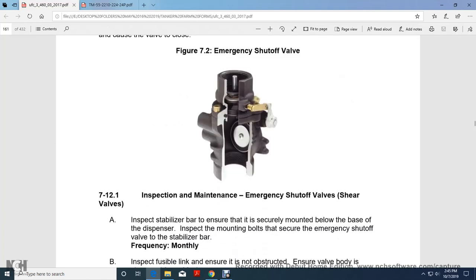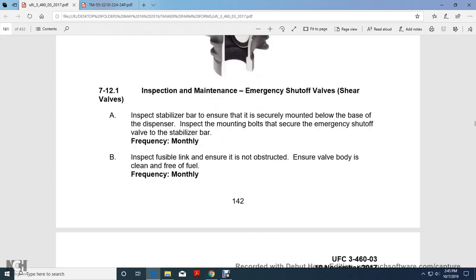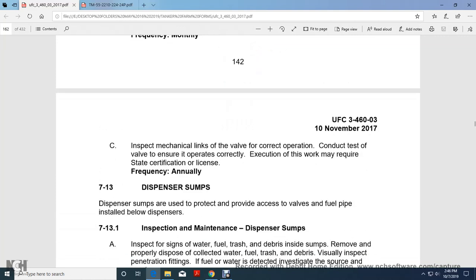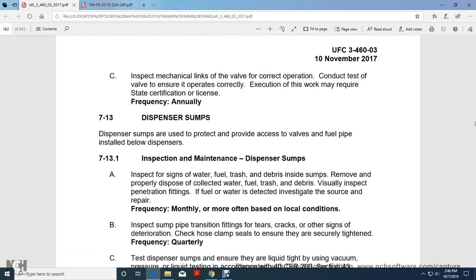Should the emergency shutoff valve. Alright, inspection maintenance, emergency shutoff shear valves. Install stabilizers and ensure that they are securely mounted below the base of the dispenser. Inspect the mounting bolts for the secure mounting of the emergency shutoff valve with the stabilizer monthly. Inspect the fusible link, ensure that it is not obstructed, and ensure the valve body is clean and free of fuel monthly. Inspect mechanical links for the valve for correct operation, and conduct a test of the valve to ensure that it operates correctly.